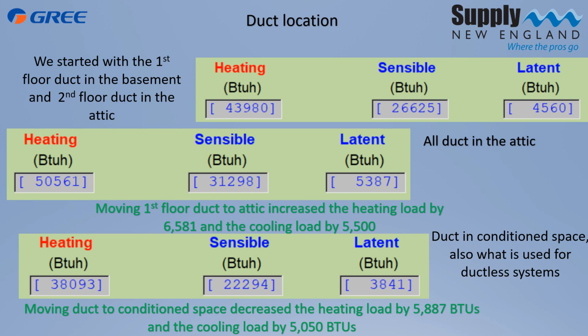Now our duct location. In our original design, it's a single system with 2 zones, one in the basement, one in the attic. Our second floor duct is in the attic, the first floor is in our basement, and that's where our original numbers come from. Just moving our first floor duct to the attic increases our heating load by over 6,000 BTUs and our cooling load by over 5,000 BTUs. Yes, I did put it as R8 insulation, tight duct. No matter what we do, there is going to be some heat loss and heat gain in an attic duct system. Putting the duct into a conditioned space, and look what happens. We decreased our heating load by almost 6,000 BTUs and our cooling load by over 5,000 BTUs. So make sure that you're putting your duct in the correct location if you have duct.